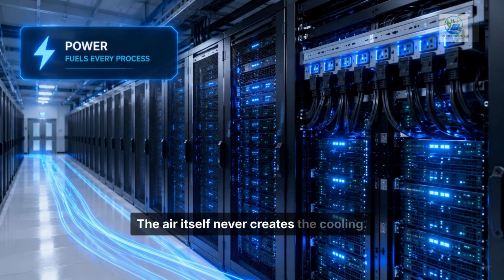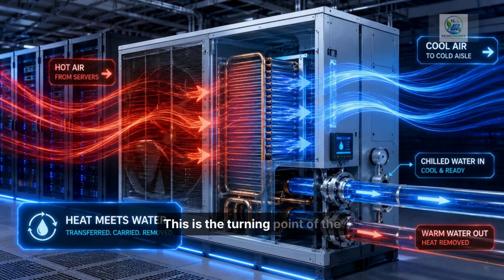The air itself never creates the cooling. Instead, it simply delivers heat to the chilled water system hidden inside the building. This is the turning point of the entire documentary. Inside the cooling coil, thousands of thin metal tubes carry chilled water supplied by the central cooling plant. As hot air passes over these tubes, thermal energy naturally flows into the colder water circulating inside. The air rapidly cools and is sent back to the cold aisle, ready to cool the servers once again.